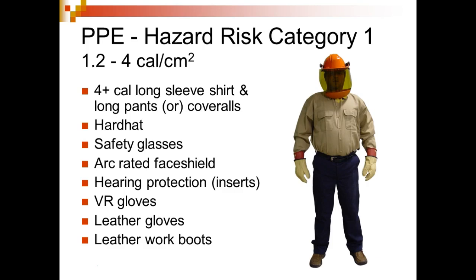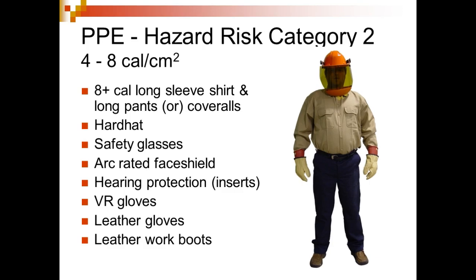Now we're used to this: hard hat, safety glasses, arc rated face shields, hearing protection, voltage rated gloves, leather gloves, and leather boots. This is 4 to 8, and this is what you've got. This looks the same, but you've got to have an 8+ calorie long sleeve shirt, so you have to start going into fire-rated clothing.